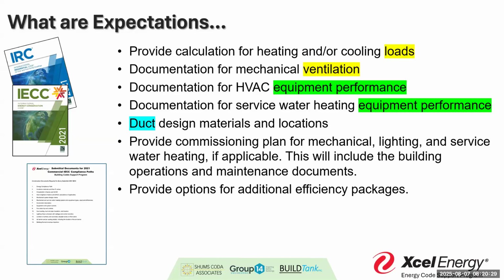There's always more than 4 things on my list, but the 4 big things I always make sure we hit are: the load calculation, and mechanical ventilation - you're going to know how much air we need in that room. One thing we're going to see, especially in residential, moving forward, is once we get into A2L refrigerants, you're going to have to know what volume of air you need in a space to reduce potential flammability issues should you have a leak. So you have to know that ventilation expectation.